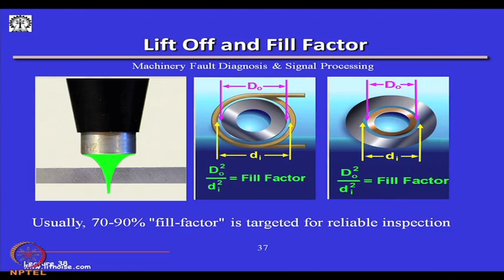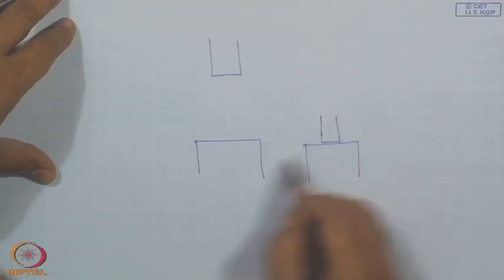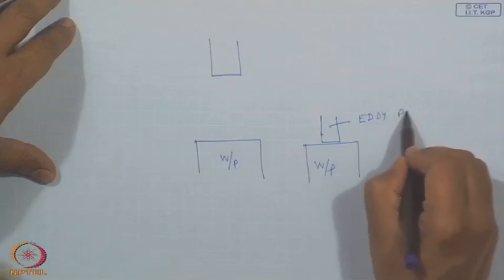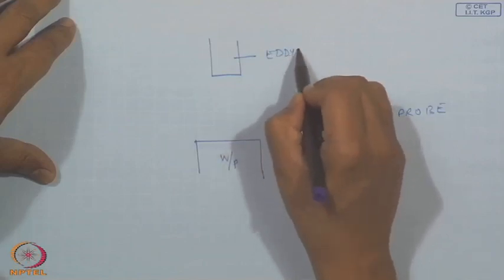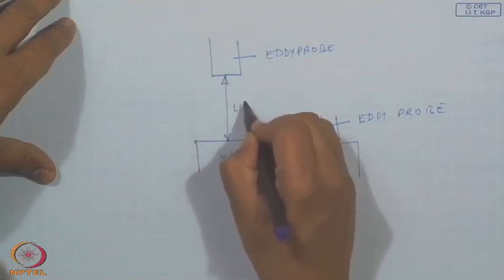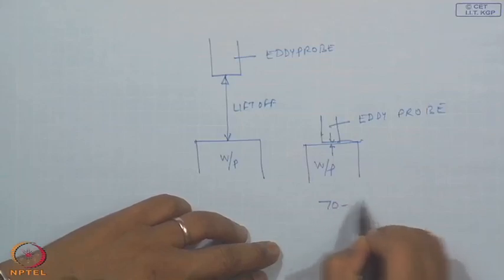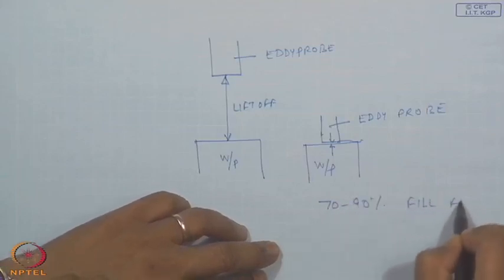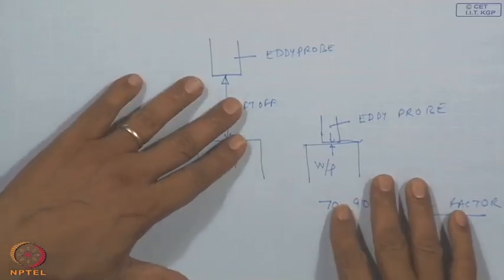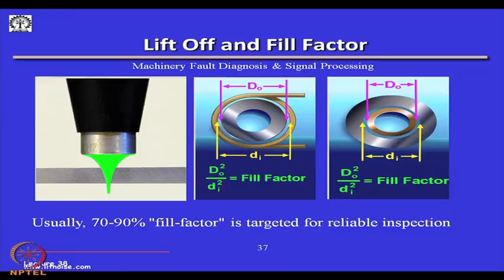You should not be too far away or too close. If you lift the probe off, the diameter ratio changes because of the lift-off. So we have to ensure we are within 70 to 90 percent of the fill factor. These kinds of experiences come from field analysis and are thumb rules to keep in mind while measuring.